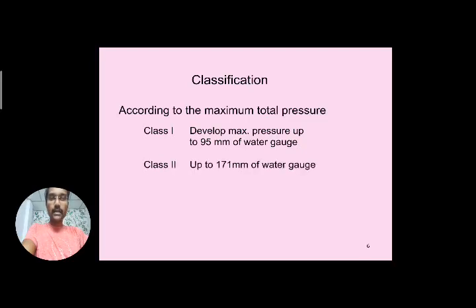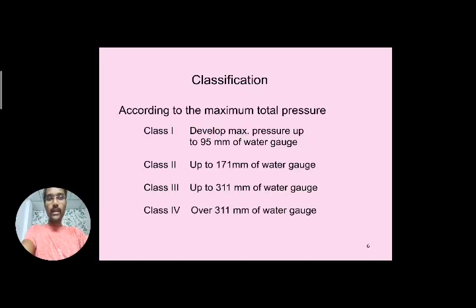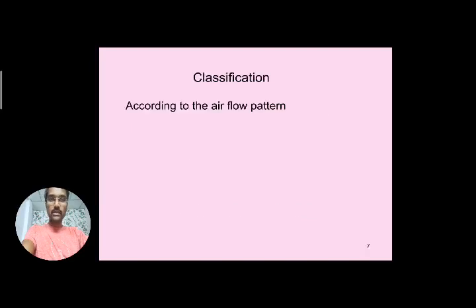According to maximum total pressure, fans are divided into different classes: Class 1 develops maximum pressure up to 95 mm of water gauge; Class 2 up to 171 mm of water gauge; Class 3 up to 311 mm of water gauge; and Class 4 is over 311 mm of water gauge.